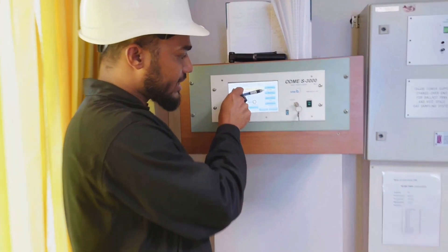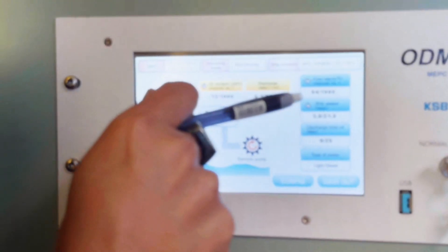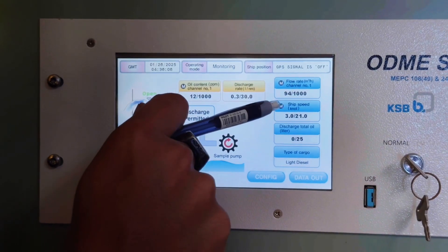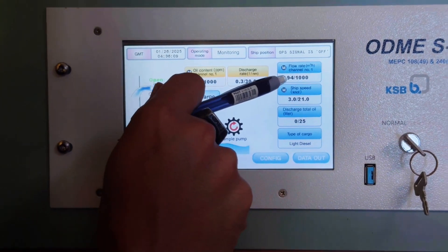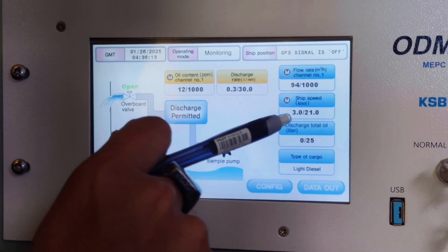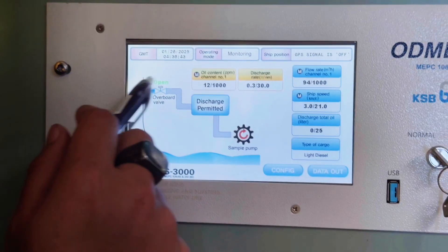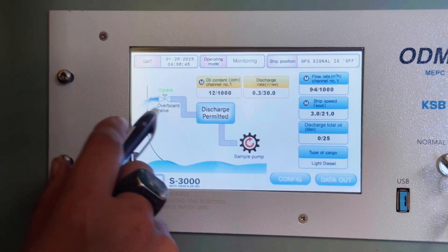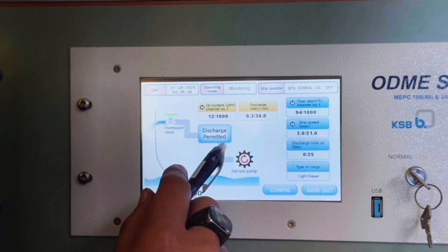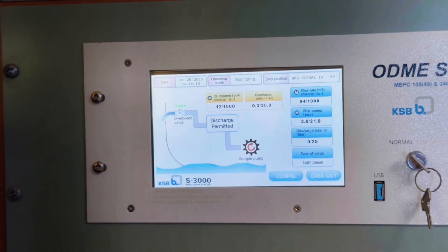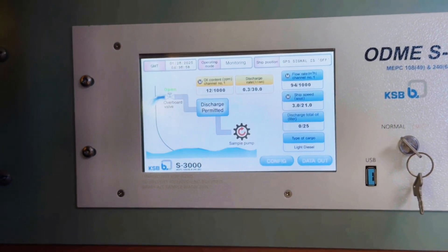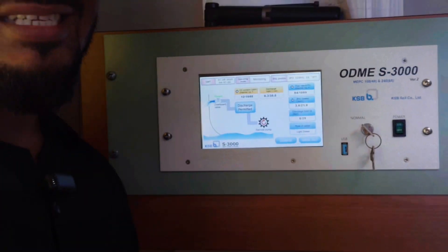This is the input data you can see: flow rate as we input — 94 cubic meters per hour. Ship speed is 3 knots as we input. So in this video we can see that the valve remains open and 'discharge permitted' is shown. That is the simulation of the ODME — verifying that the overboard valve automatically opens with the correct setting.